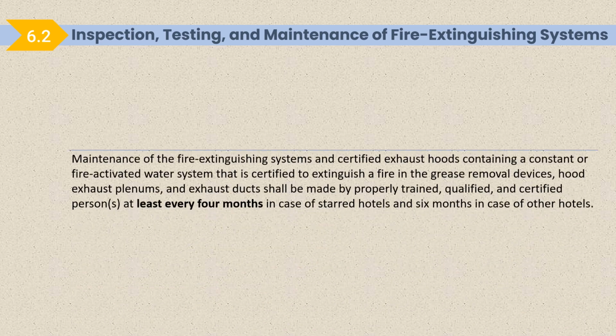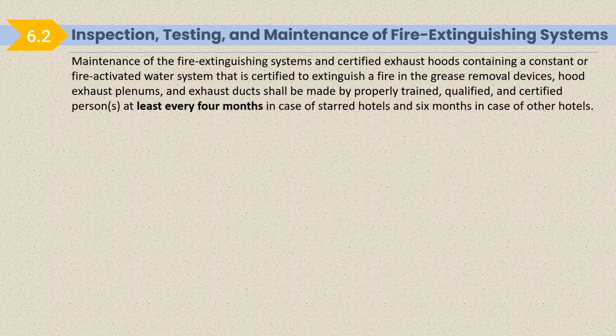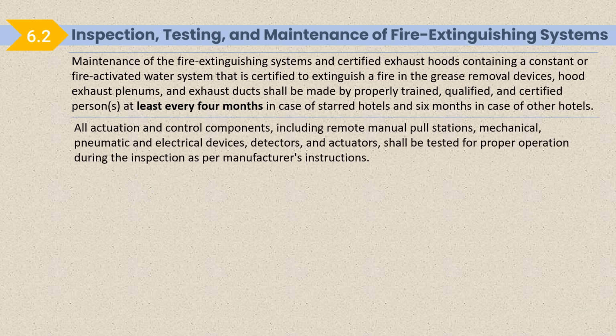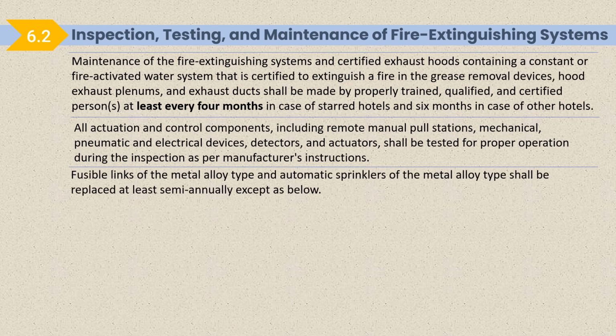Inspection, testing and maintenance of fire extinguishing system. Maintenance of the fire extinguishing system and certified exhaust hood containing a constant or fire activated water system that is certified to extinguish a fire in the grease removal device, hood, exhaust plenum and exhaust duct shall be made by a properly trained, qualified and certified person at least every 4 months in case of starred hotel and 6 months in case of other hotel. So it depends upon the use. We will talk about the frequency of cleaning also. All actuation and control components, including remote manual pull station, mechanical, pneumatic and electrical devices, detectors and actuators shall be tested for proper operation during the inspection as per manufacturer's instructions.